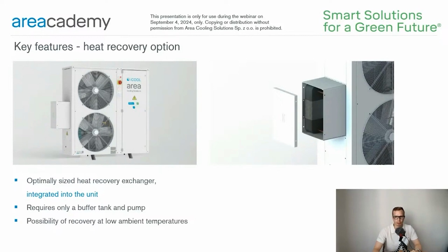This is a fully equipped system with an optimally sized plate heat exchanger. The entire process is managed by the controller, and it allows to reclaim the heat from the high pressure side, giving you the flexibility to use it for heating domestic water or glycol, among other possibilities. By taking advantage of the high heat recovery potential from CO2 with this intelligent heat recovery system, you will reduce energy bills.